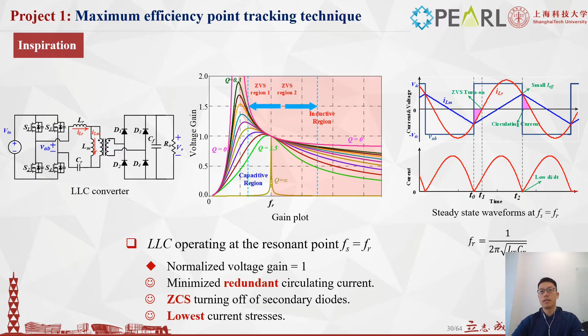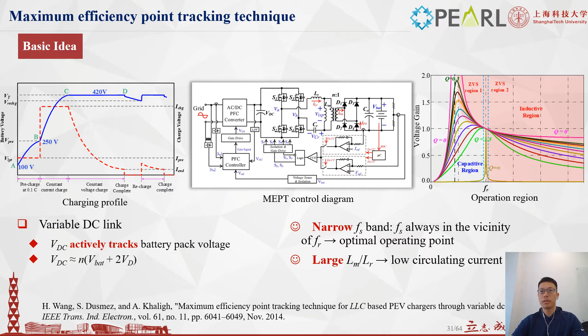Inspired by this, we proposed the maximum efficiency point tracking technique. Instead of a constant DC link voltage, we adopt a variable DC link voltage to actively track the battery pack voltage. Therefore we can effectively narrow down the frequency band and make sure the switching frequency is always very close to the resonant frequency, as shown in this region. So we can declare that the LLC topology is always operating at its optimum operating point. Besides, we can have less requirement on the buck function of LLC, so we can adopt a large inductance ratio. A large LM means we can use a large magnetizing inductance, which helps us further reduce the circulating current.